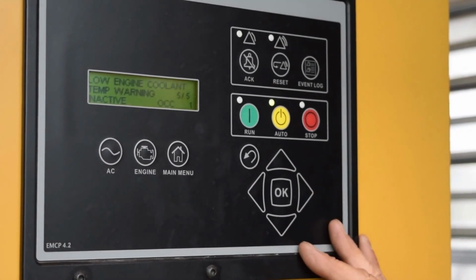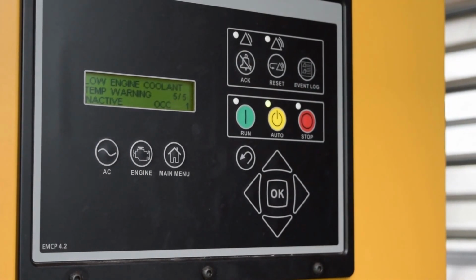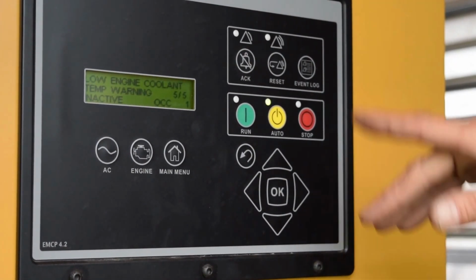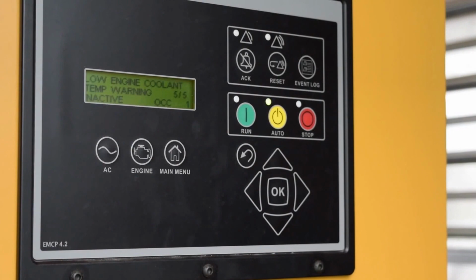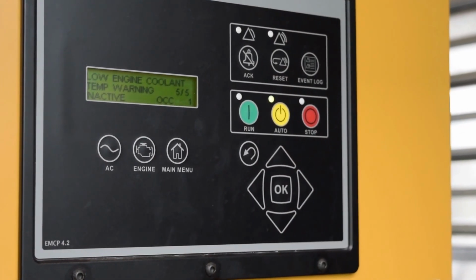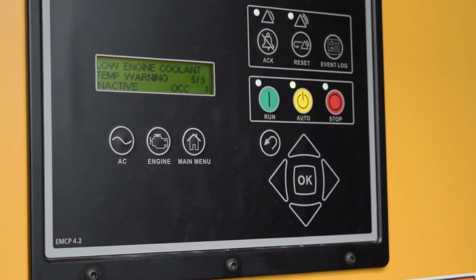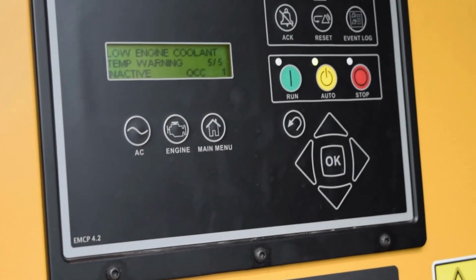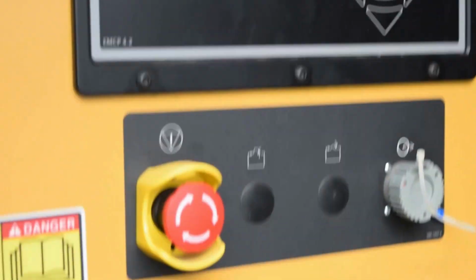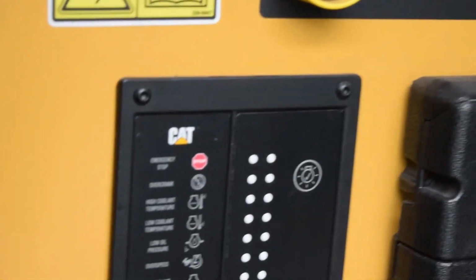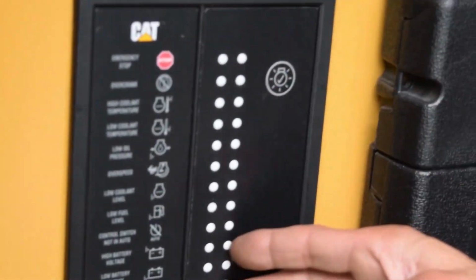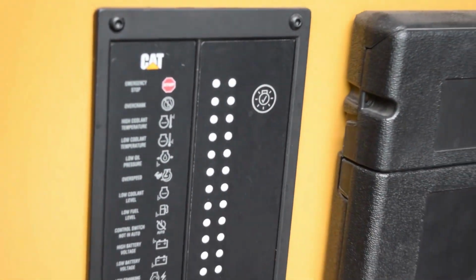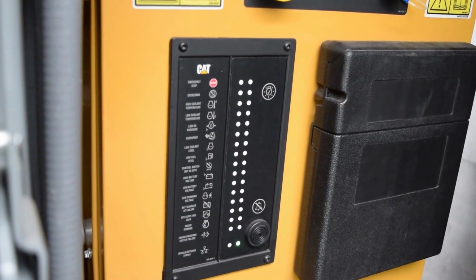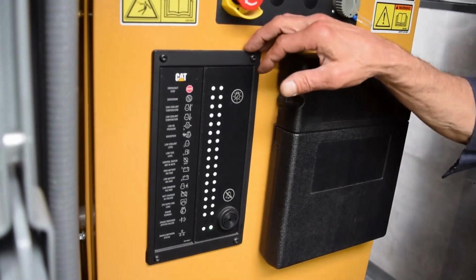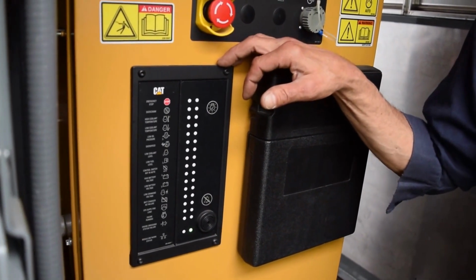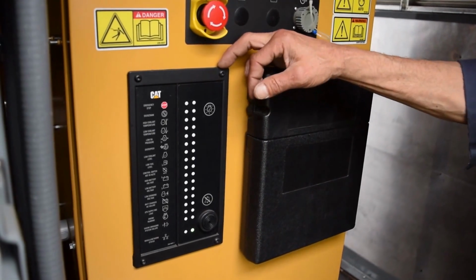They may have shut the power off for this for a little while at one point in time. A lot of those codes seem to be that. If a warning comes in, all your major warnings and shutoffs are all right here on your annunciator. You'll get an amber light on one side for a warning and a red shutdown on the opposing side if it is a shutdown. This is also down in the Fire Command Center, replicates everything that is up here.